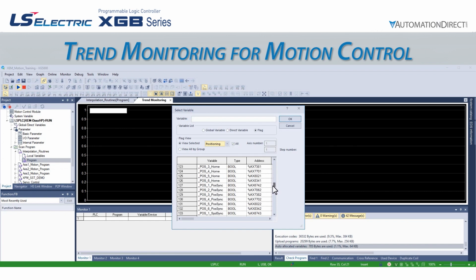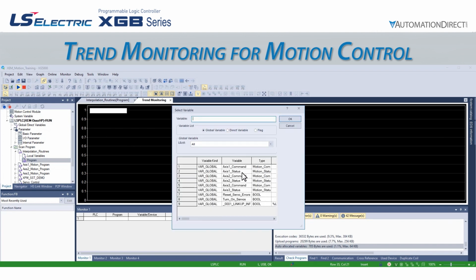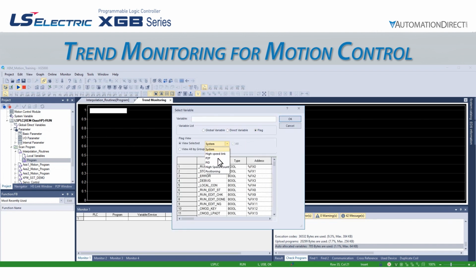This will display all the positioning flags in the PLC. If we scroll down, we can find the flag variable _pos_1_curpos. This flag will display the first axis's current position in real time. We can select OK and then add the _POS_2_CurPos and select OK twice to add these variables to the trend graph.